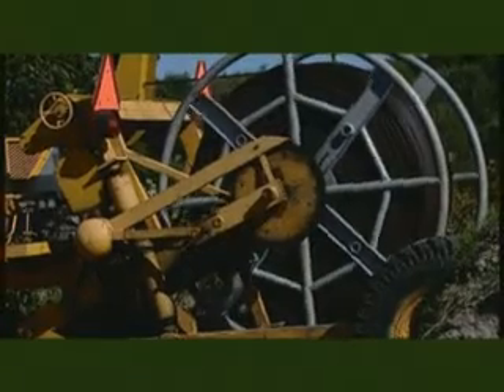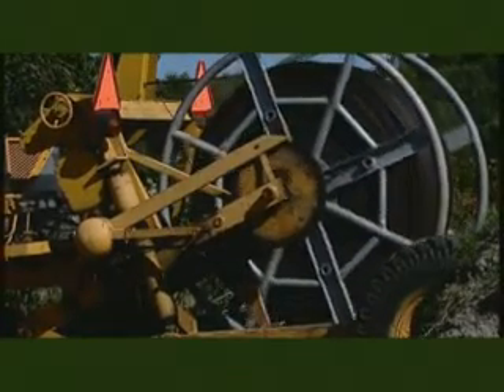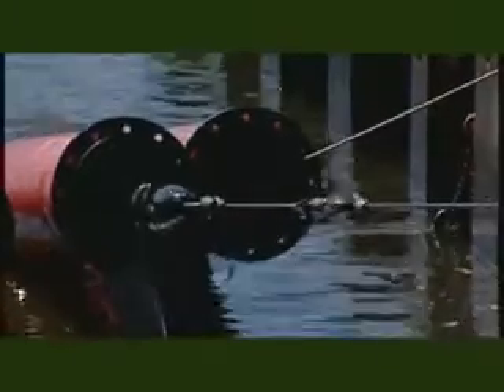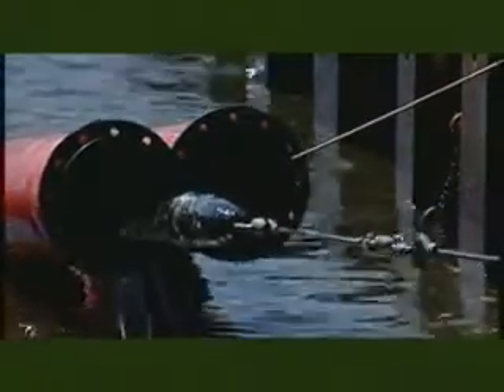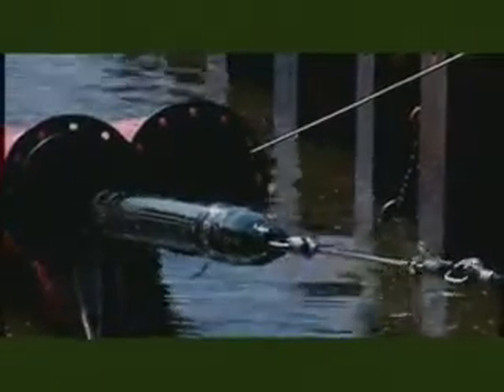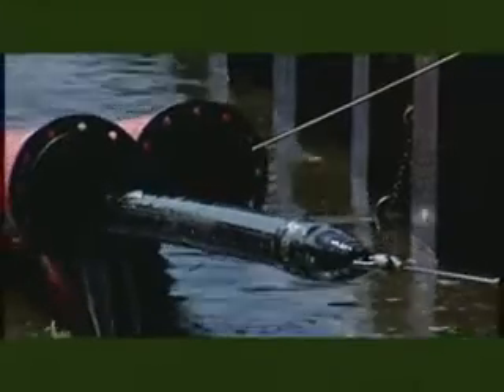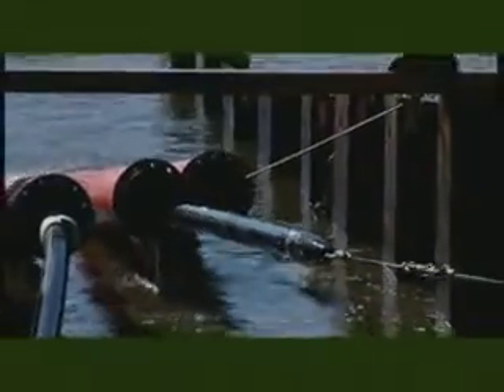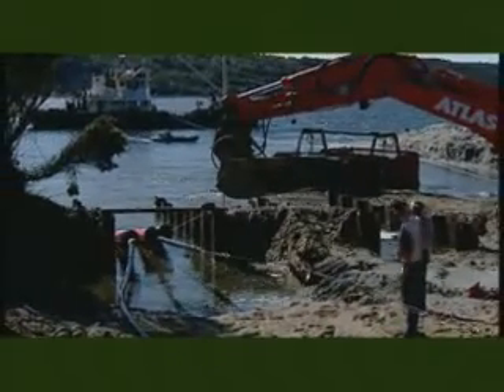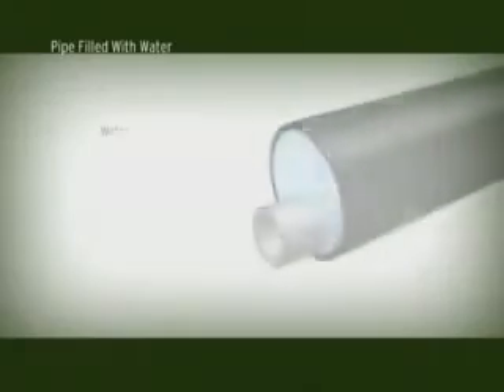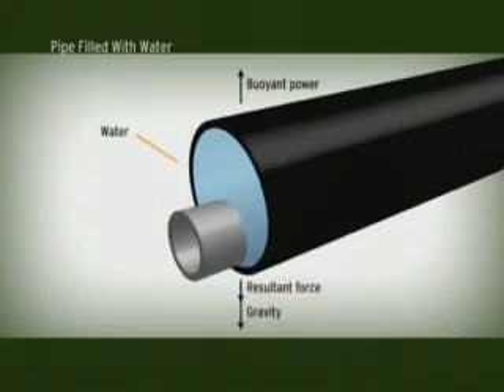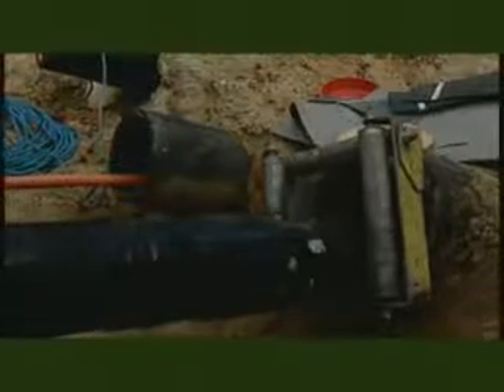The maximum permitted traction on the submarine cables is 4,800 kilograms. The tensile force is monitored at the winch. The maximum pull on the cables when they're being pulled through the pipes is measured as being 2,800 kilograms. As the pipes are filled with water, the cable is buoyant. There is thus minimum friction between the cable and the pipe. Moreover, soap is smeared onto the cables at the opening to the long directional drillings.